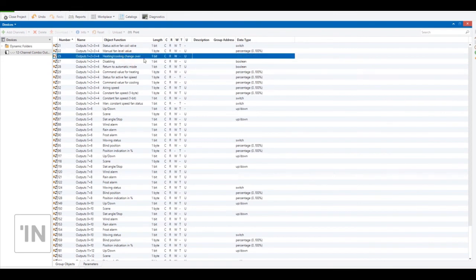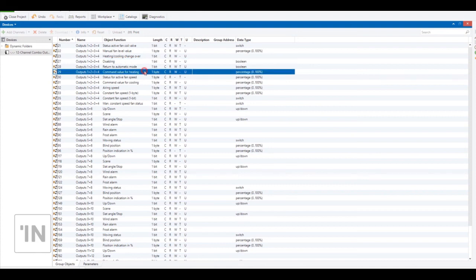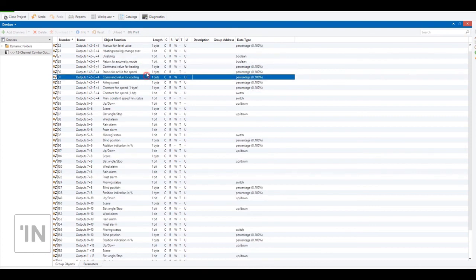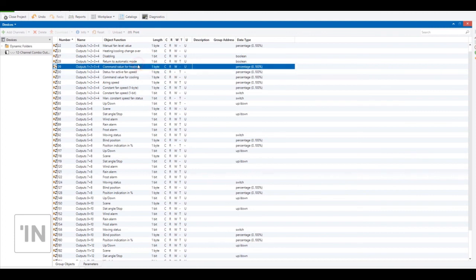Heating/cooling changeover: when you send a one-bit value of zero, it activates cooling; when you send a one-bit value of one, it activates heating. Disabling object: if you want to turn off fan coil control completely, you can use this object. When you send one for this object, it turns off fan coil control completely. Using this object you can control a fan coil basically.